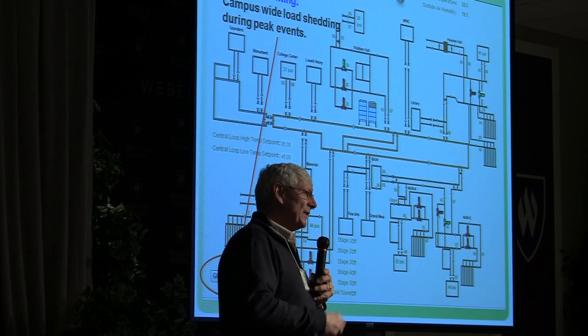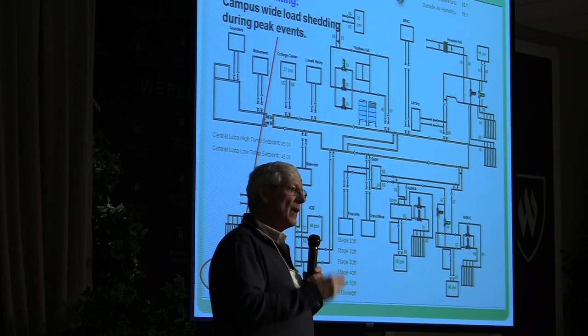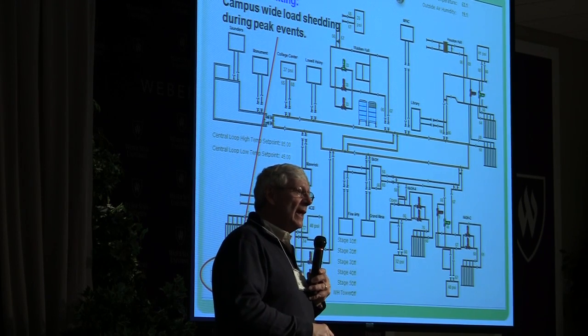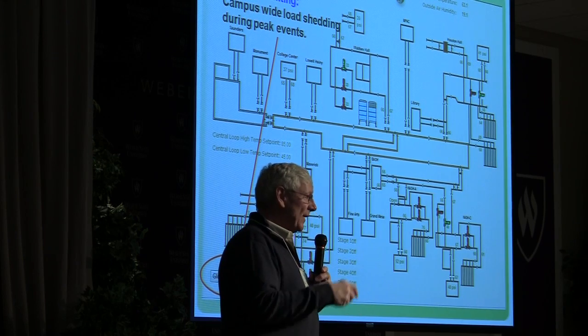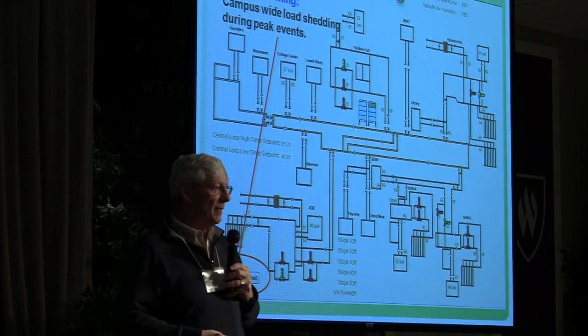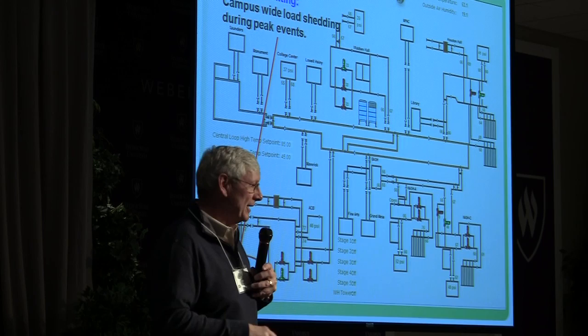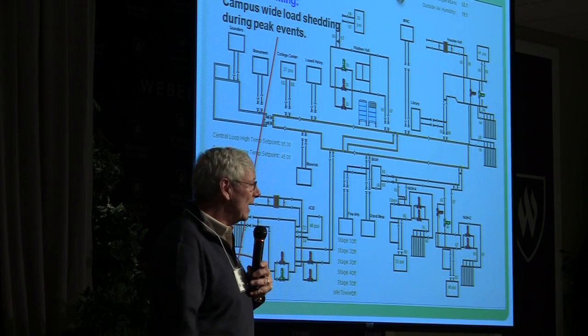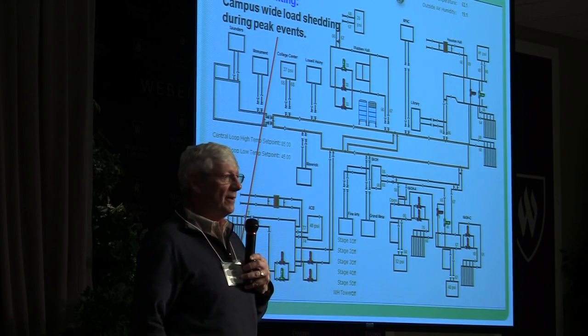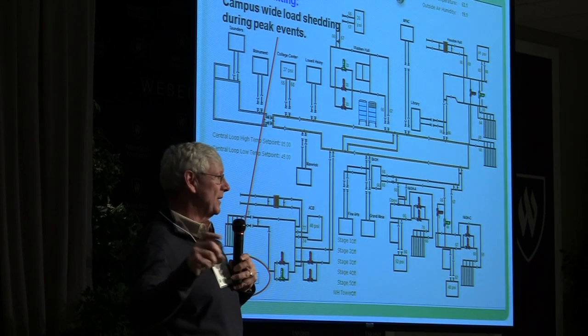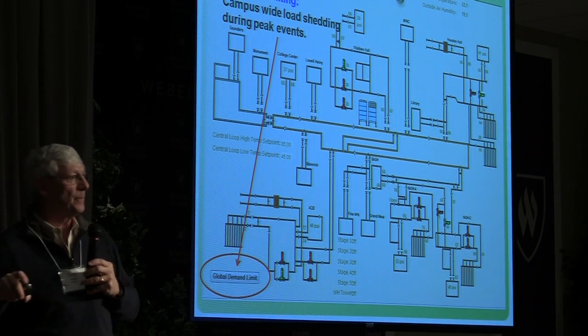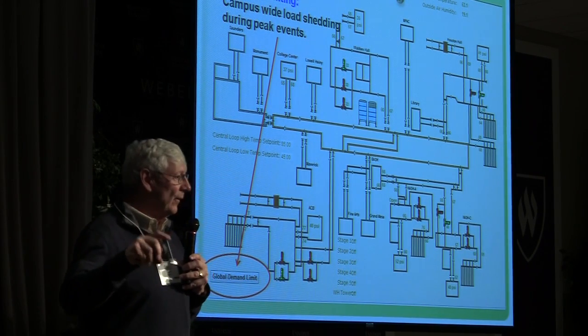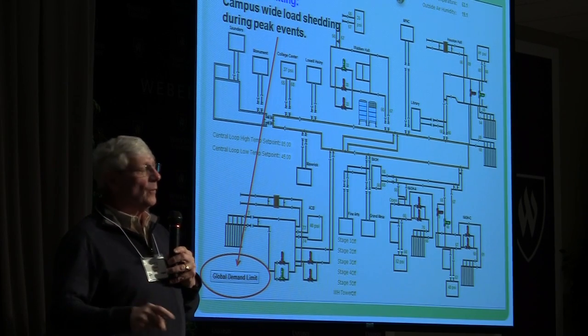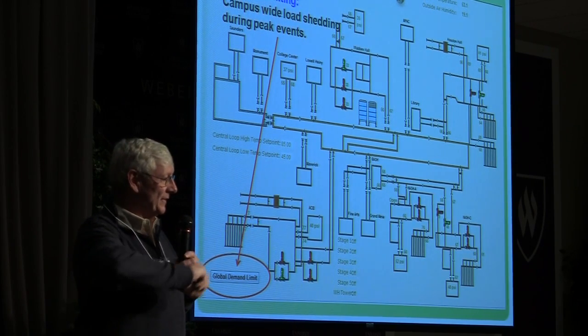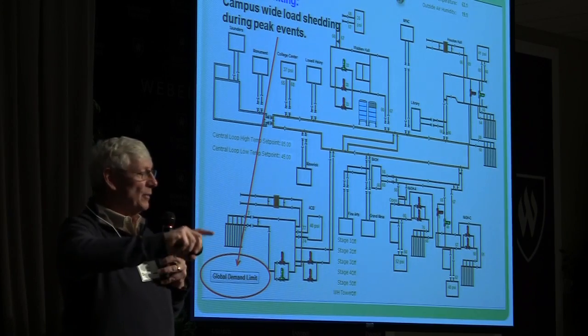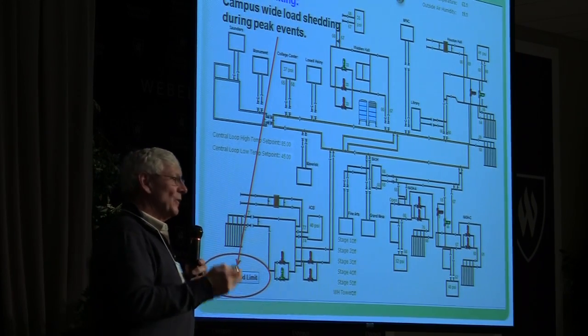The story goes, I wasn't there but I was told, and there's no reason not to believe it, that when the facilities manager got the call, he hit the global demand button. We'd never really done anything to measure with it, other than exercising it. And 15 minutes later, Tri-State could see the reduction in demand, 230 kW, just like that. So it's a huge tool, and looking at the sum for all of the buildings, the size of the demand limiting we did was somewhere between $5,000 and $10,000 for the bonus check.